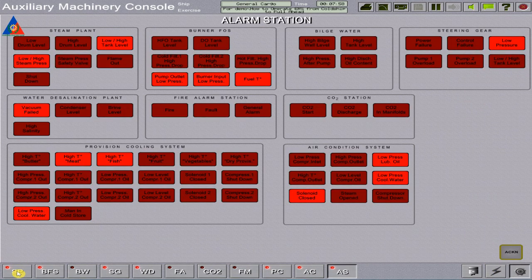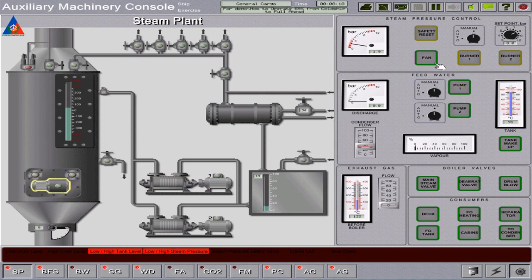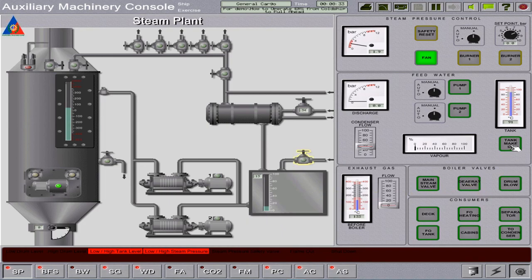Proceed to the auxiliary machinery console to start the steam plant. First, close the deaerating valve and turn off feed water pump one before we fire the boiler. Start the boiler fan to purge gases inside the furnace. Then fill up the condenser tank to at least 80% capacity by opening the tank makeup.